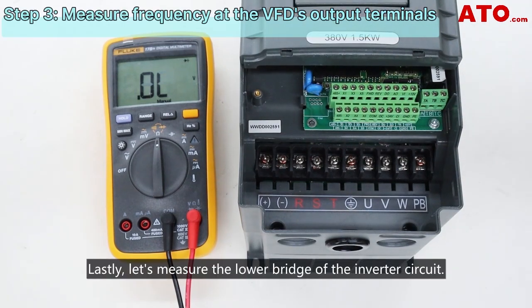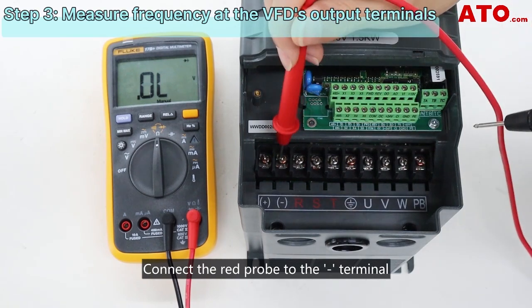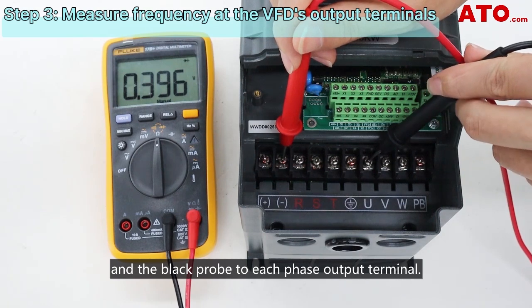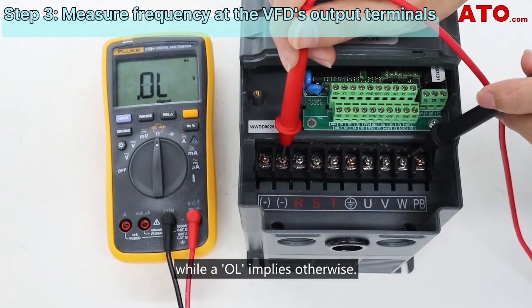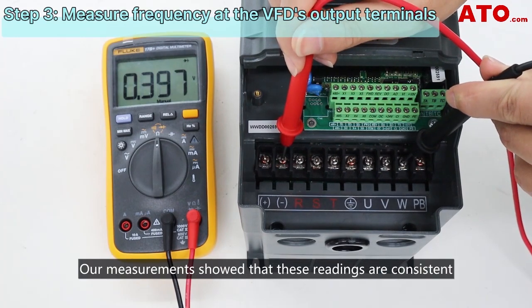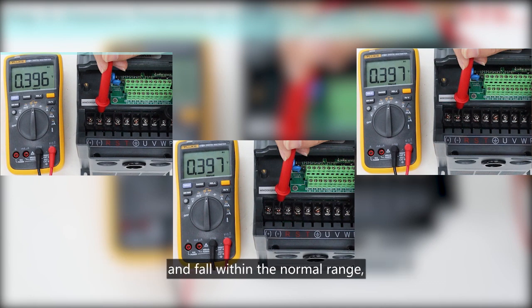Lastly, let's measure the lower bridge of the inverter circuit. Connect the red probe to the minus terminal and the black probe to each phase output terminal. The reading around 0.4 volts confirms proper functioning, while an OL implies otherwise. Our measurements show that these readings are consistent and fall within the normal range, indicating that the VFD is free from any issues.